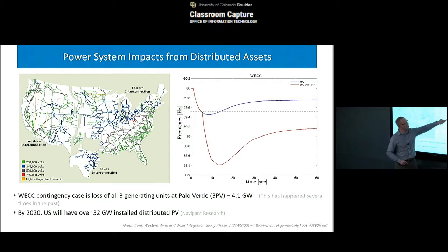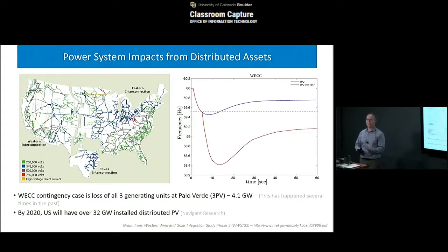So this is, the blue is the normal case of a large contingency, and note you're all the way down to 59.4 here. If the distributed PV kicks off, you're down at 58.6. That is unheard of. That is virtually impossible. Well, it's not impossible, it just never happens because everything shuts down before then. Okay, so that shows the impact that that could have.